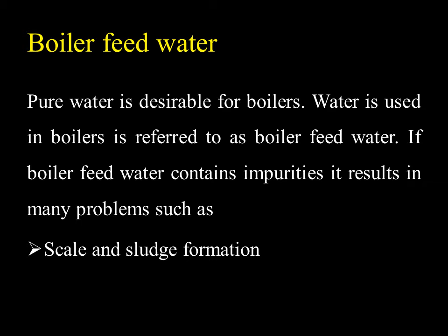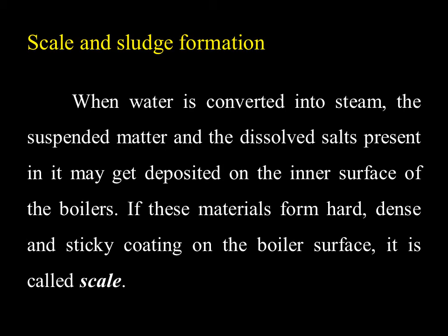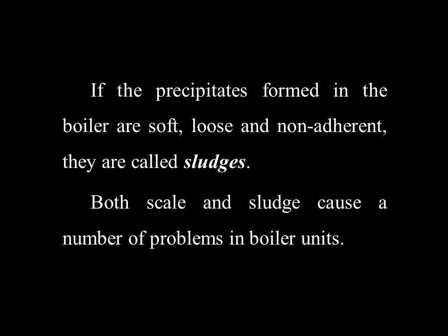Okay, so let us try to understand what scale and sludge formation is. When the water is heated to form steam, the suspended matter as well as the dissolved salts present in the water get deposited on the inner surface of the boiler, irrespective of the size of the particles. If these materials form a hard, dense, and sticky coating on the boiler surface, it is called scale. If the precipitates formed in the boiler are soft, loose, and non-adherent, they are called sludges. Both scale and sludge cause a number of problems in boiler units.